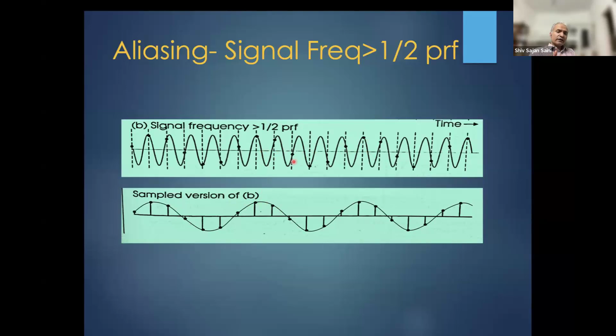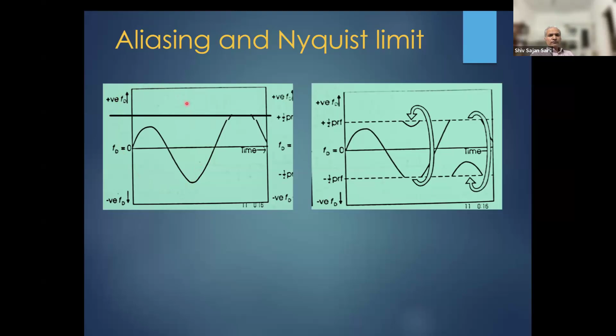So what is aliasing? Now this is the Doppler shift which is going to be depicted. This is the half pulse repetition frequency, which is our Nyquist limit. Anything which is above this Nyquist limit is not going to be represented, and it is going to come as an add-on signal above. I'll show you how. This is how you see it on the screen. This is the actual image. This is the diastole, this is the systole.